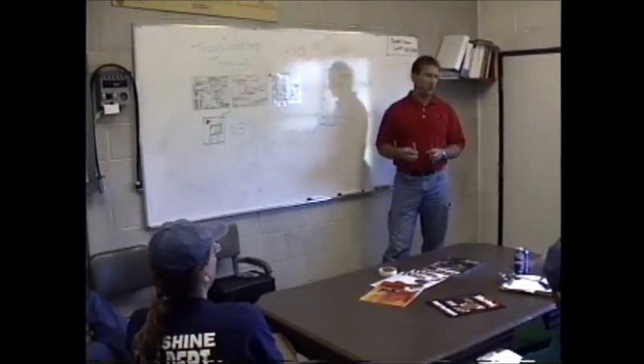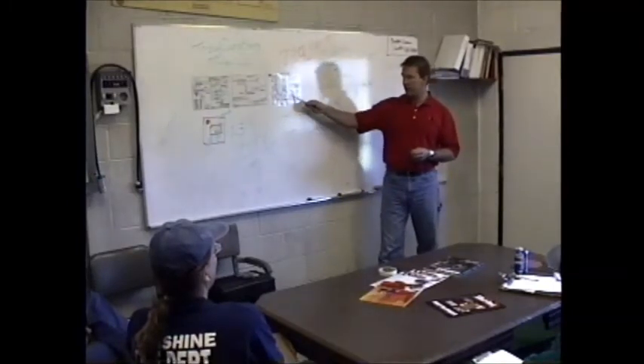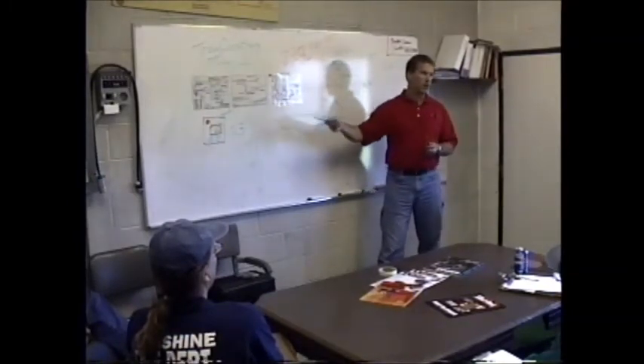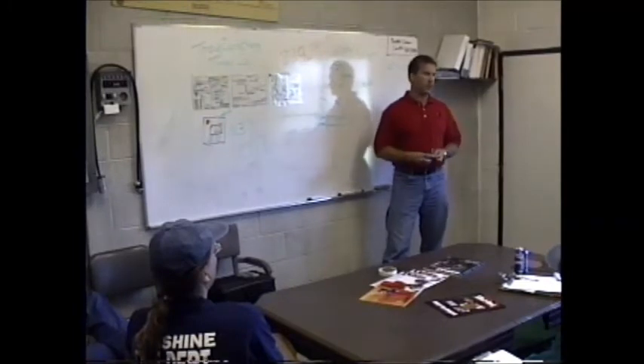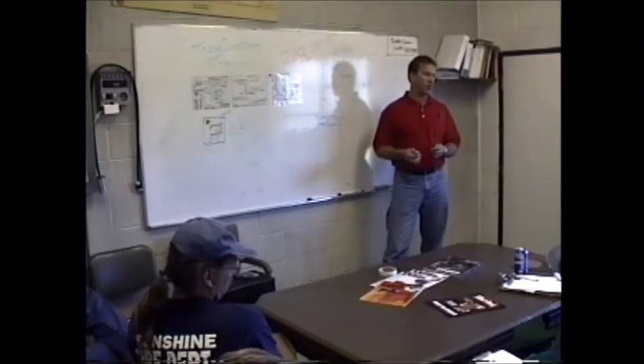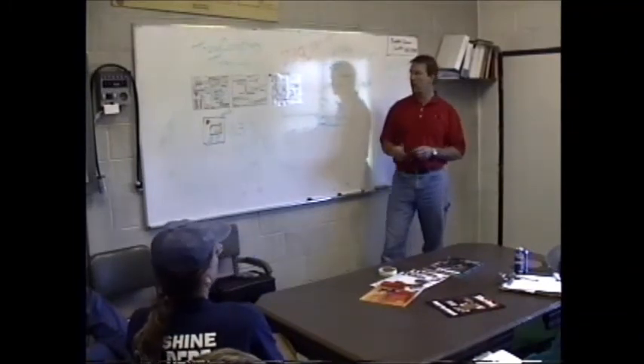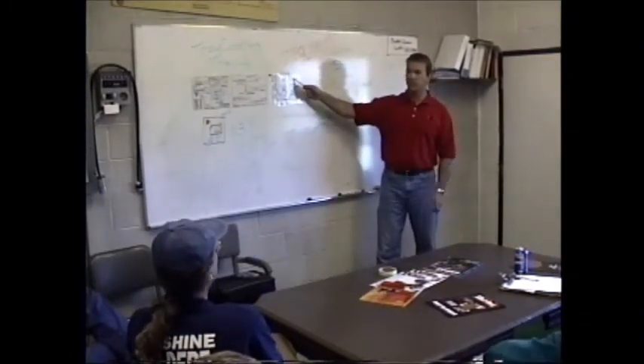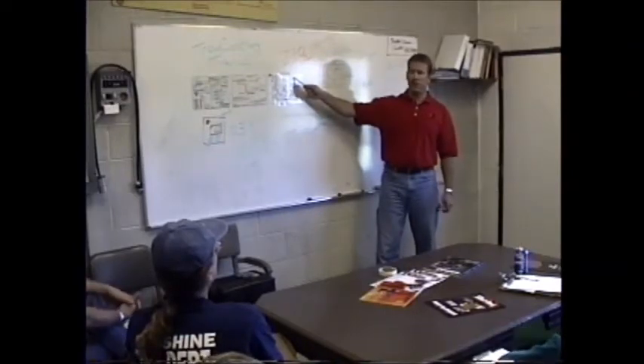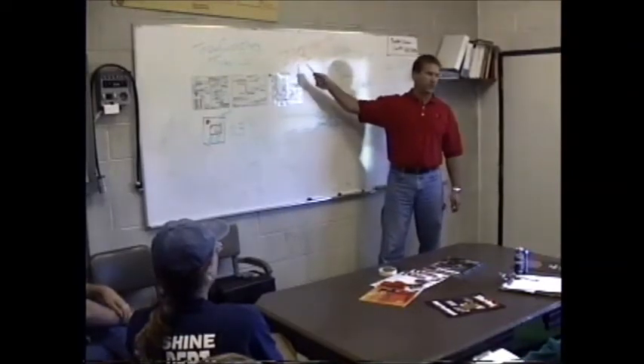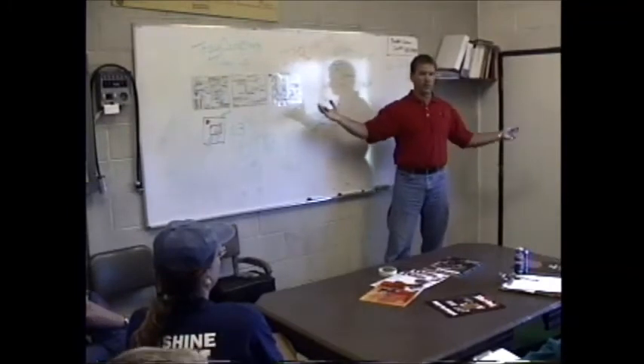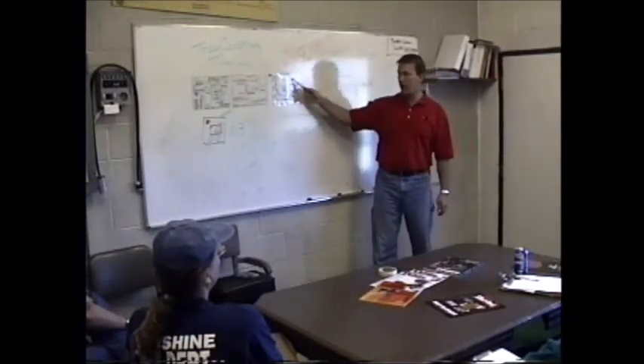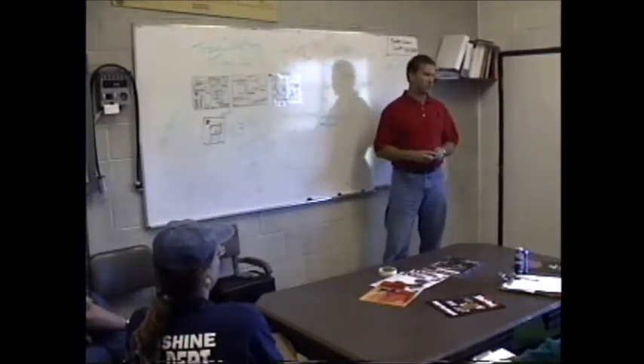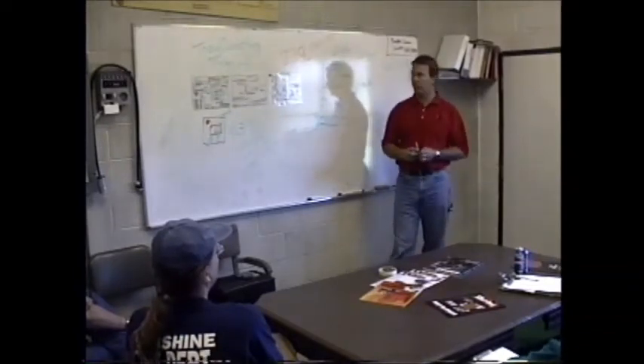So therefore we've set more stringent maintenance guidelines. We'd like to see the oil filter and the oil changed every year, but if it hasn't hardly been used, it's overkill. I don't like to see people waste their time or money on oil and oil filter changes if it's not necessary. The most important filter in the whole system is your air filter.